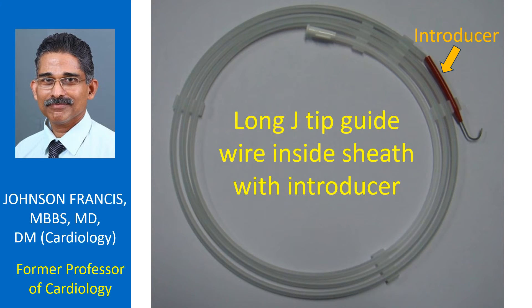The thickness of the guide wire depends on the type of application. Guide wires for PTCA balloons are very thin, of the order of 0.014 inch, while guide wires for catheters are 0.032 to 0.038 inch.